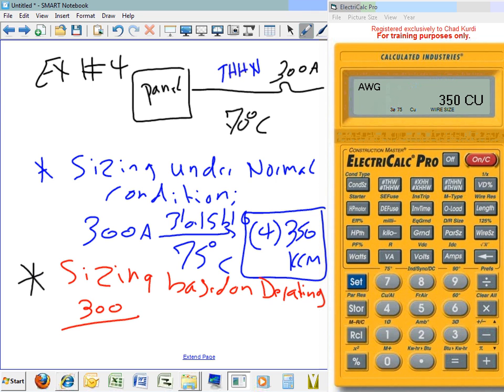This is on page 150. For 70 under 90, 70 row, column 90, you should be able to come up with 0.58. Everybody came up with 0.58? Cool. Okay, so divide this by what? 0.58. Now, Nick, why do we divide? Because we have a load and we're sizing a conductor. That's what we normally do. If we have a conductor and we need to find a load, we multiply.